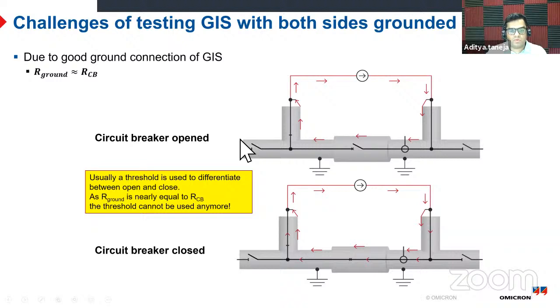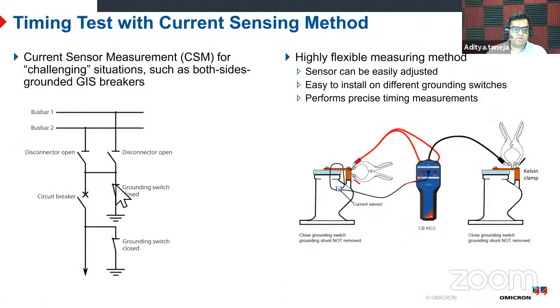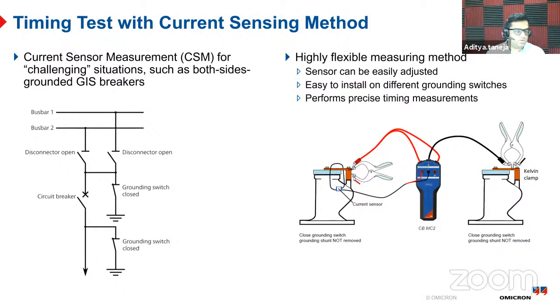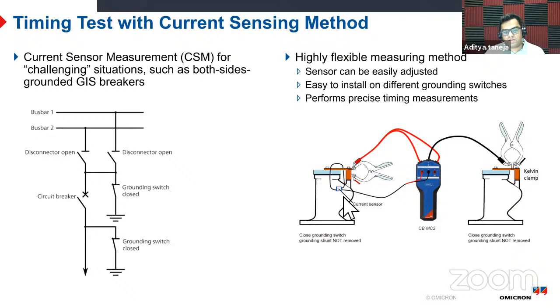What we do in this case is we leave the ground switch connected, no problem, and we put an inductive coil across the grounding loop. So this is the grounding of the GIS, the grounding links from a GIS. This is an example from Siemens drawings, but you will have different designs for different breakers and different voltage levels. If I give examples of Hyundai or Hyosung, at 110 kV in Saudi Arabia they have all three phases coming out, and a strip bar is there. For 380 kV, they have individual tanks for individual phases, so they have different grounds.